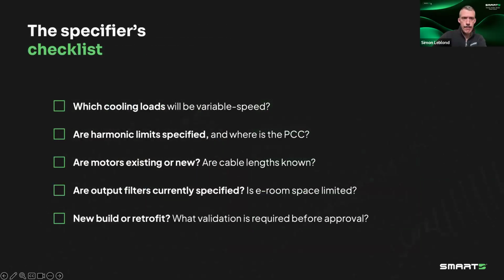So 43 minutes in, I'm going to speed up. I'm almost done. As you go through your spec, go through the checklist of: what are the loads that are variable speed, what are your harmonics limits specified at the PCC, are you working in a retrofit or an existing situation, or a new build with existing motors or new? What are your cable length constraints? And do I need some filters here? What kind of space do I have in my electrical room?